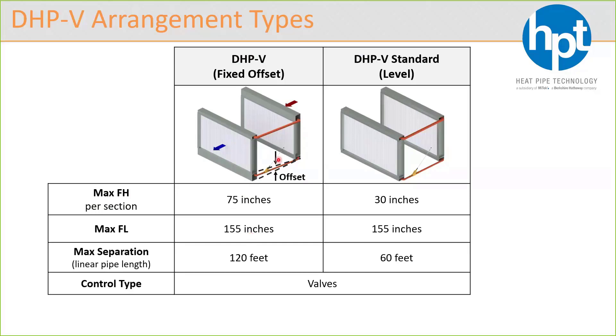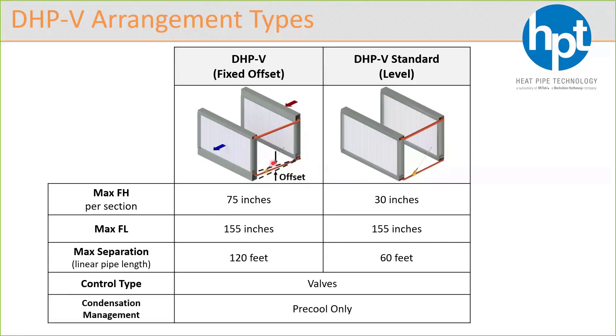For control type, we offer modulating valves, which is actually one of the bigger advantages for DHPVs compared to our other controllable wraparounds in Select Plus with level tubes. Depending on system size, it may be more cost effective to use a DHPV compared to a level controllable wraparound because at a certain point you get too many valves with level wraparounds, whereas DHPVs have far fewer circuits and valves. For condensation management, you're really just worried about the pre-cool condensing, so you'd want an extended drain pan or moisture eliminator downstream of the pre-cool. More information is available at heatpipe.com or by reaching out to us.